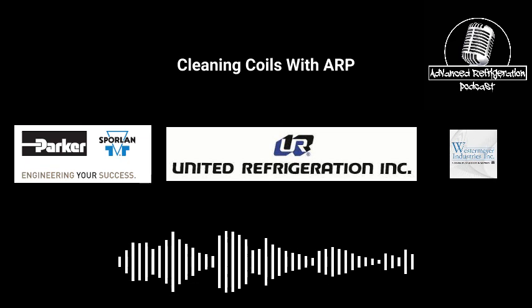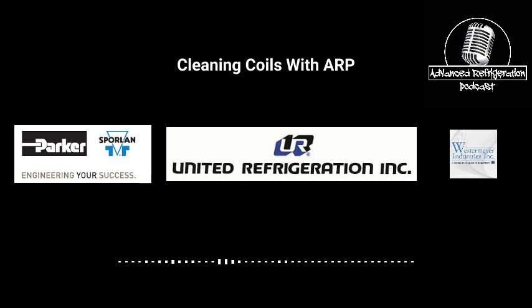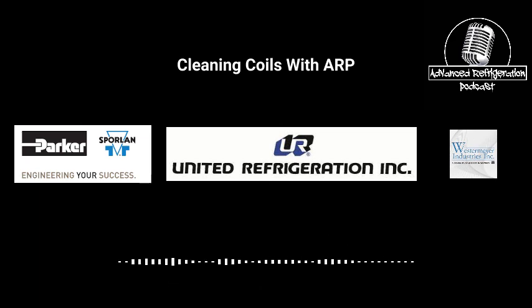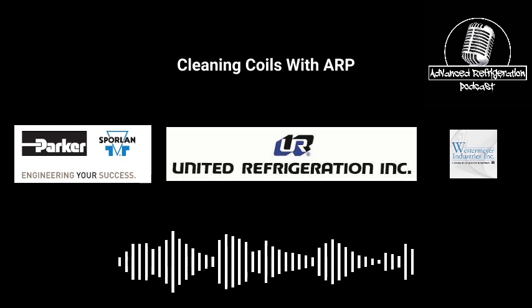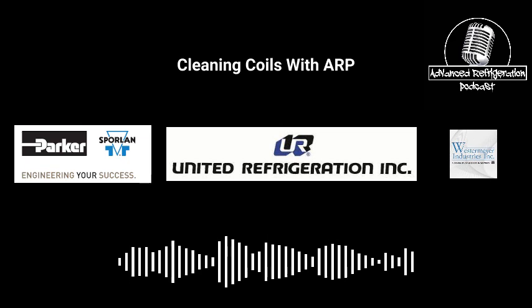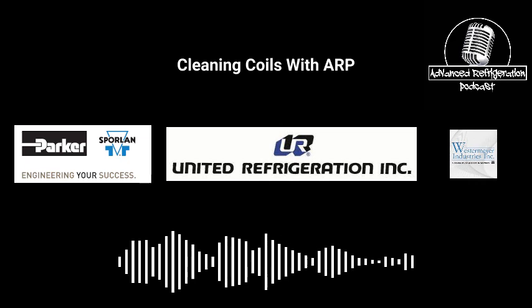Lennox units are just V's. Those have doors, so you need to clean it from the inside out. Same with AAONs. A lot of AAONs are microchannel coils. When it comes to microchannel coils, guys, you can't use cleaner on those. Viper makes a cleaner for it. They're the only one I know of to make a microchannel cleaner. It works pretty well. You don't really need pressure on those. We've had a couple we pressure washed, but you need to be very careful with it. Use a real wide pressure washer wand so you're not putting too much in one spot and making a leak. But you absolutely don't want to use Nu-Calgon coil cleaner on microchannel coils. You're going to want to clean those with usually just a hose.